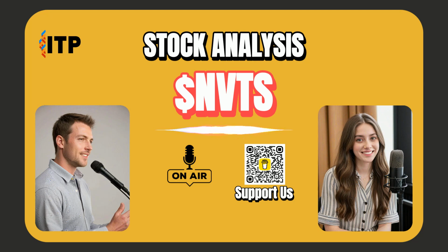Gigawatts. And the old ways of getting power to the chips inside the racks? It's just not cutting it anymore. They're hitting serious limitations. Traditionally, you might distribute power inside a server rack at, say, 54 volts. That was fine for a while, maybe up to a few hundred kilowatts per rack. But now racks are drawing much more—way more. As you push towards a megawatt per rack, or even beyond, that 54-volt approach requires incredibly thick, heavy copper cables to handle the sheer amount of current.